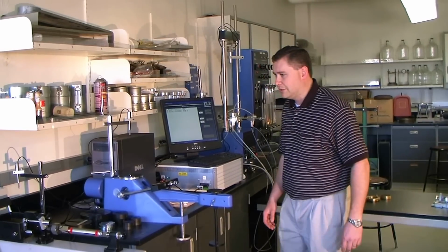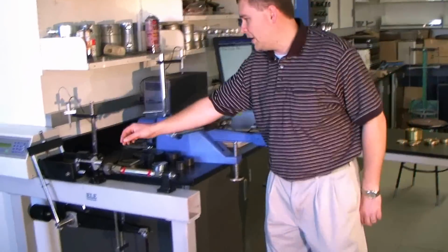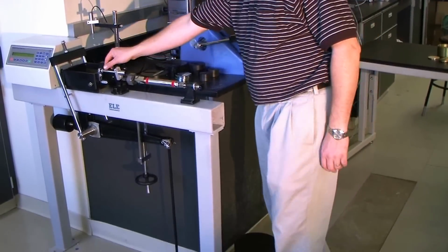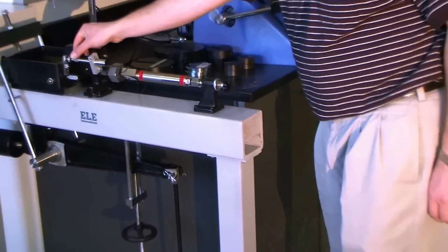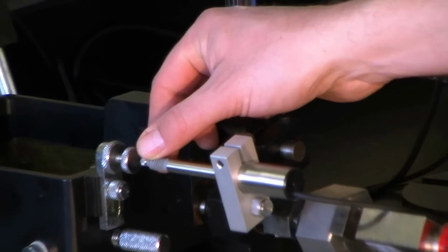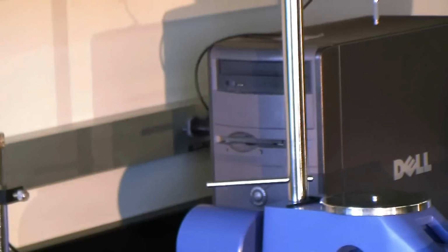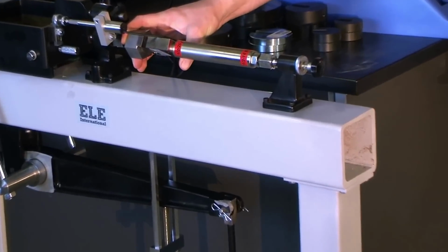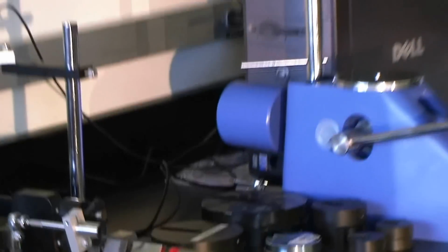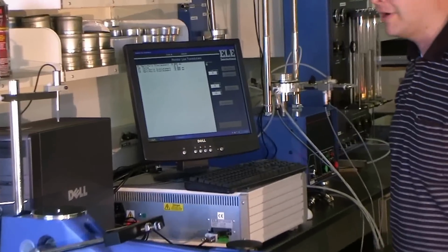So for the horizontal one, as we mentioned, we want this to read positive with the piston going in. So as we move the piston in, we're reading positive values on the monitor transducer screen, which is very good. So it's reading the correct way. The force, we can just verify the force. You can take it off and put a known weight on the force transducer to verify that it's reading right, but it's reading positive going in, which means the polarity is correct.